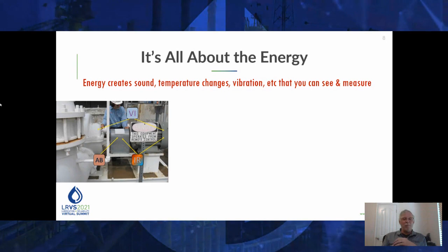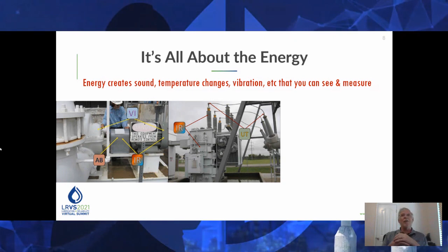And the interesting thing about energy is if you give it an option, it's going to go where you don't want it to go. If there is a problem in that bearing because you didn't lubricate it properly, the energy that is supposed to be going down the shaft is now going into the balls and becoming hot. Same kind of situation: you're doing infrared surveys on the transformer. You might have corona effects that you cannot see with the naked eye, but you can hear with the ultrasonic noise survey. Those corona arcs are energy that's going in places you don't want. If you have uneven heating on those insulators, that's energy going where you don't want it, and eventually can lead to a failure.